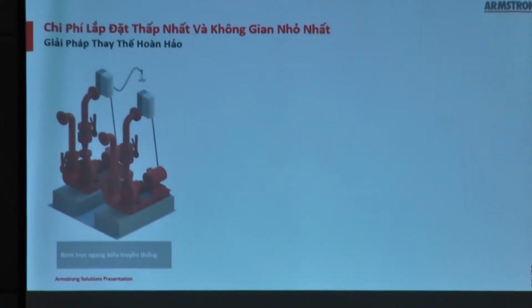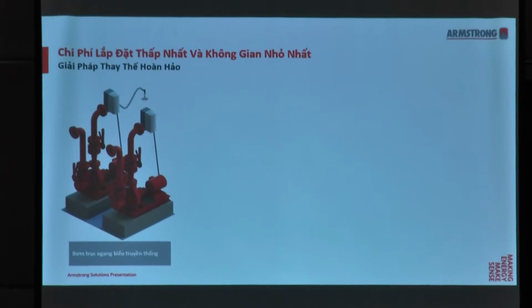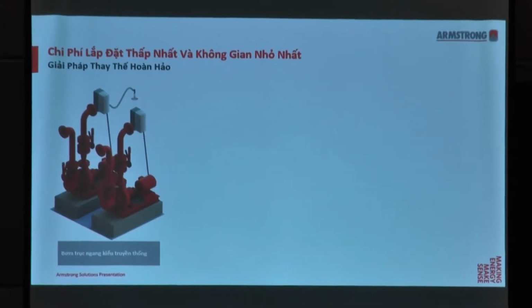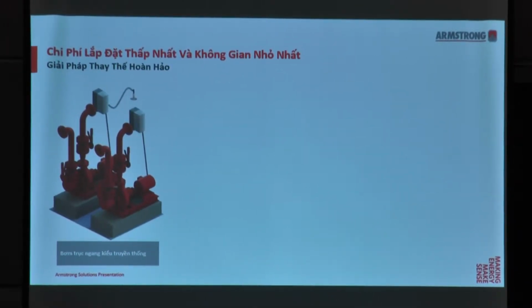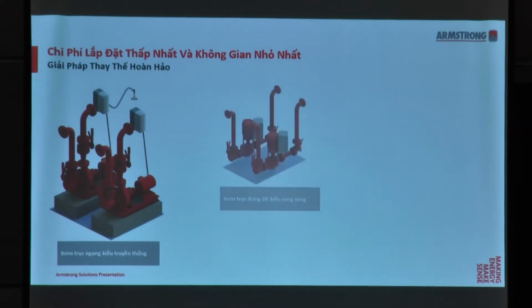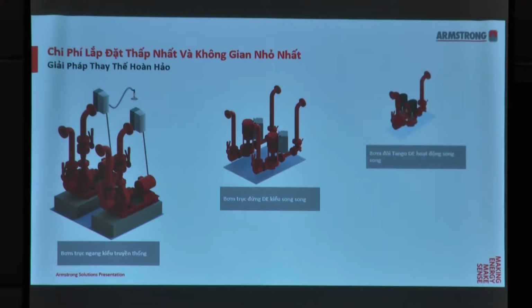Okay, so again, just to recap, if we were to consider what your designs are, basically, two end suction pumps with wall-mounted drives with an external DP sensor. And I introduced to you our design envelope pumps, which is vertical in line with integrated drives. Okay, and of course the last one I'll talk about is our Tango pumps, which is currently available up to 10 horsepower.